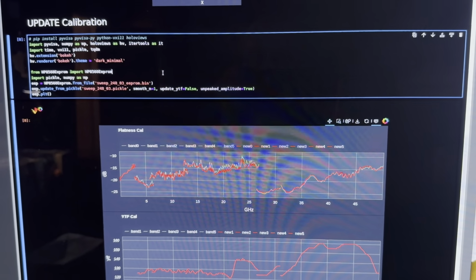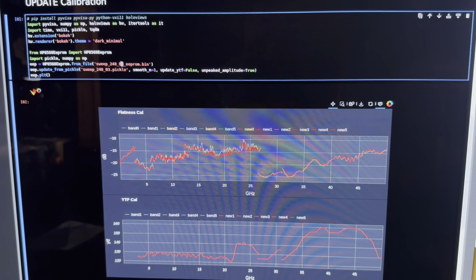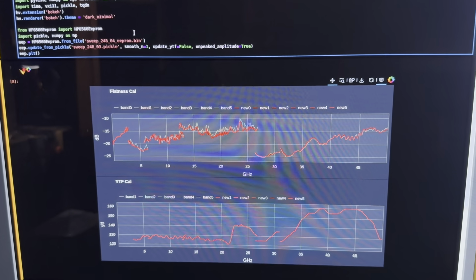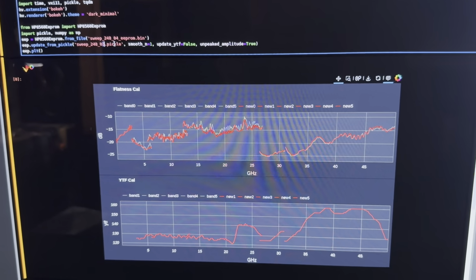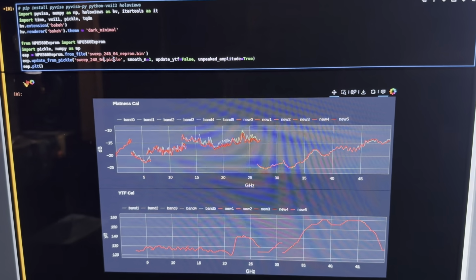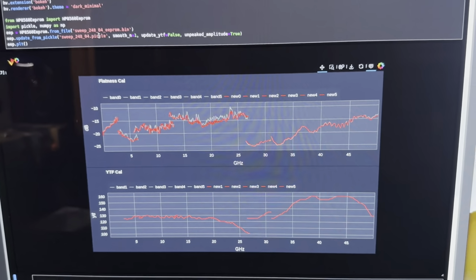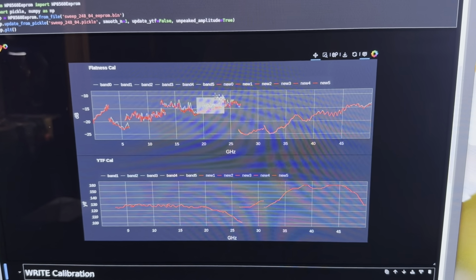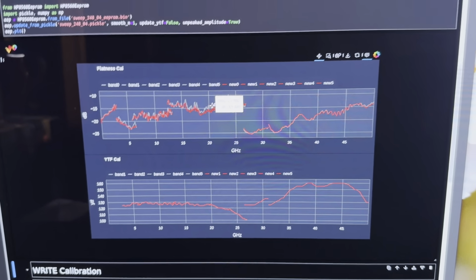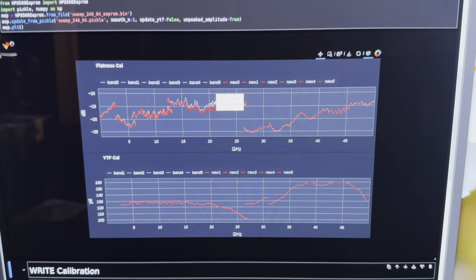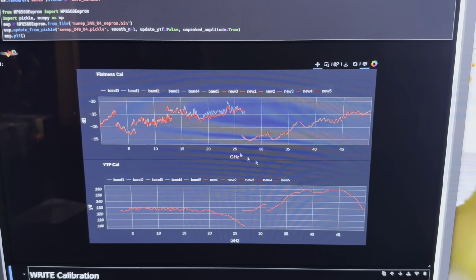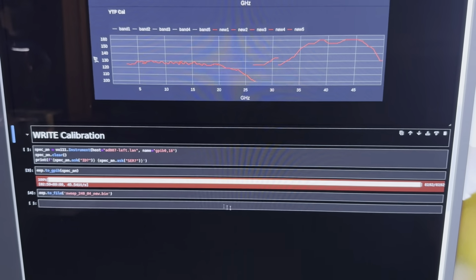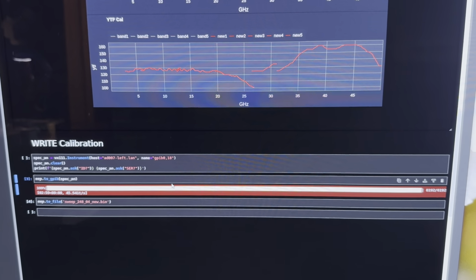And so the one last thing to do would be to take this new YTF setting and program in the observed amplitude values from this new section where we adjusted the YTF settings, right? The old measured amplitude values aren't going to be correct, so we want to take the new power sensor measurements that we took from this sweep, and we want to program them into the device.